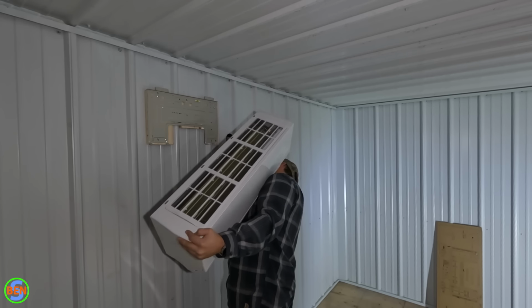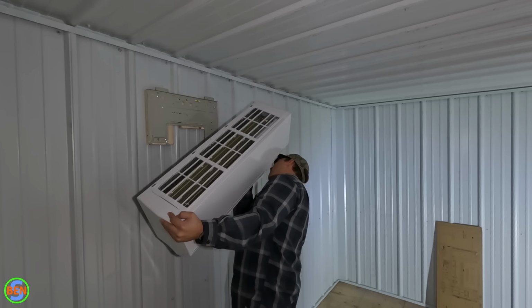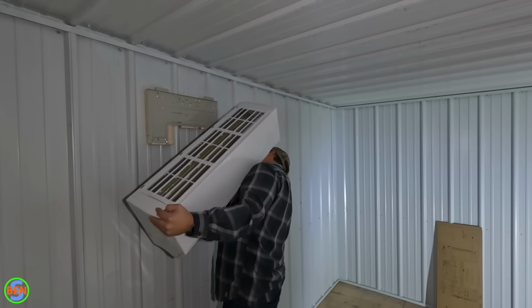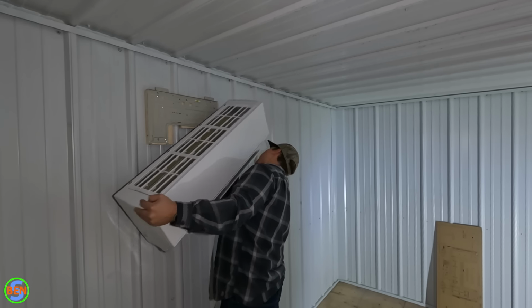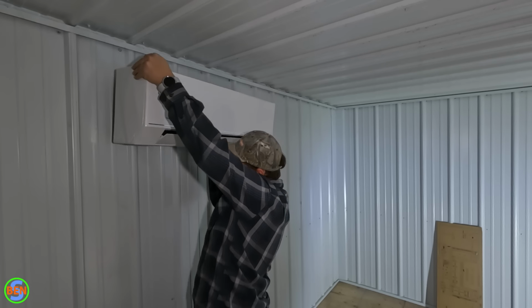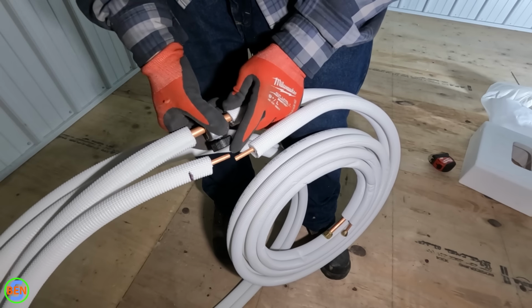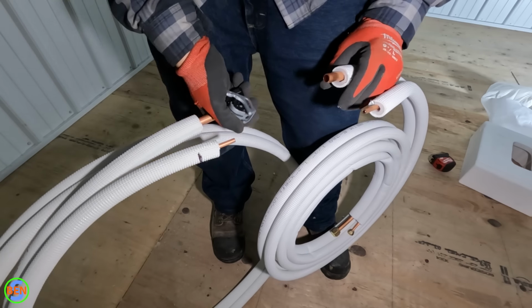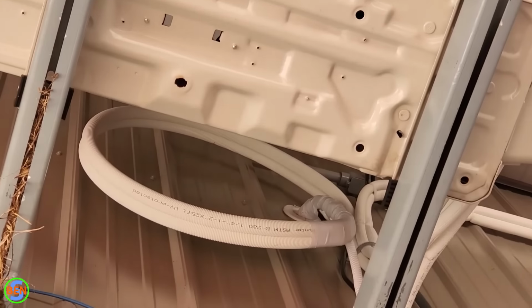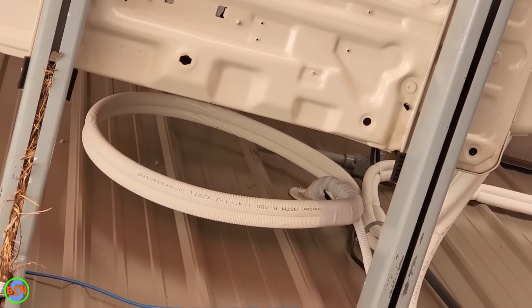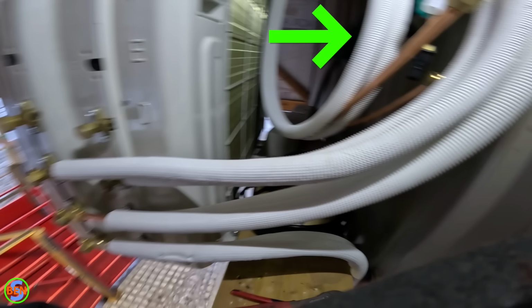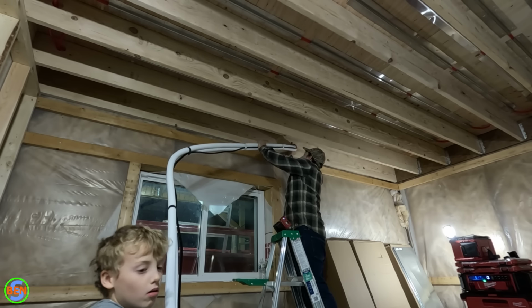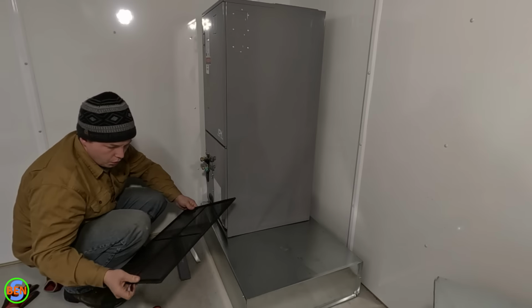You actually want to have a minimum of 10 feet of line set between where the wall unit is hung and where the outdoor unit is located, a minimum of 10 feet of line set. So what we had to do is create a loop of line set right outside next to the outdoor unit in order to prevent that line set from being too short. Now, the third location, of course, is going to be that air handler we talked about already.